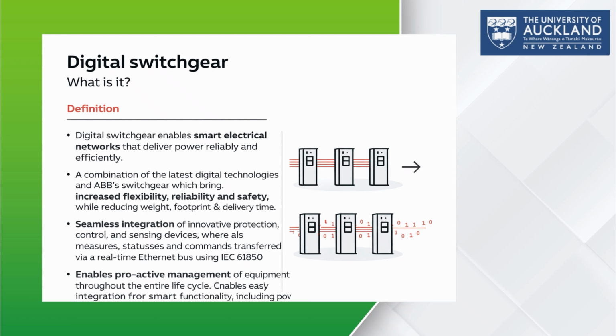And all the measurement status information and control commands are transferred through a real-time Ethernet communication bus. The most popular IEC standard is the 61850 protocol. This eliminates large bundles of copper wires and simplifies the entire communication structure. Digital switchgear also enables proactive management throughout its entire life cycle. As all data flows digitally, it supports smart functionalities such as real-time diagnostics, power management, health monitoring, and remote supervision.